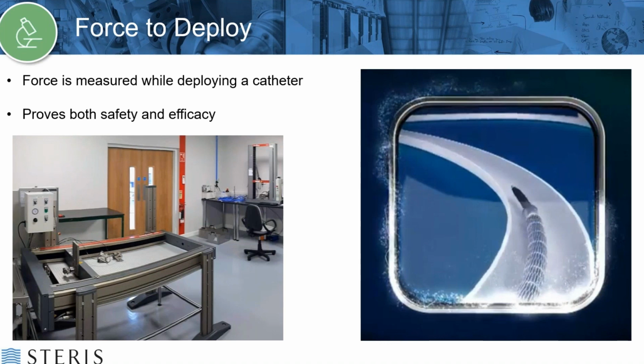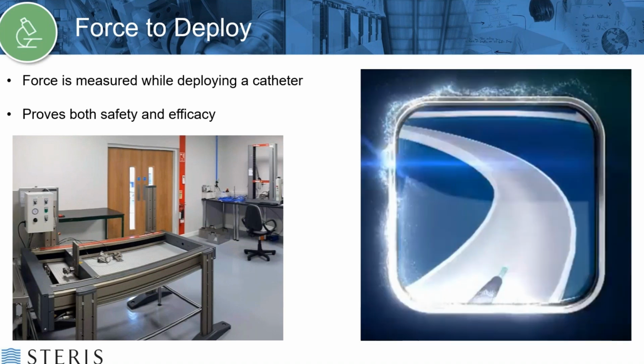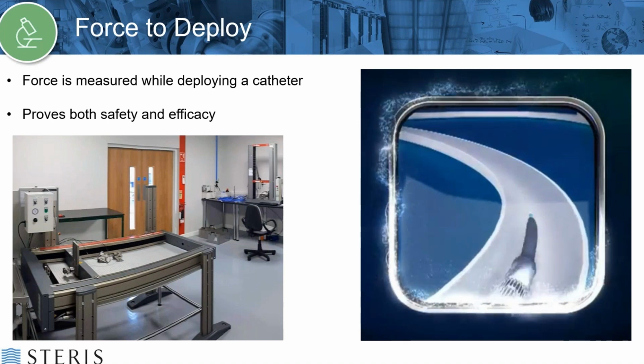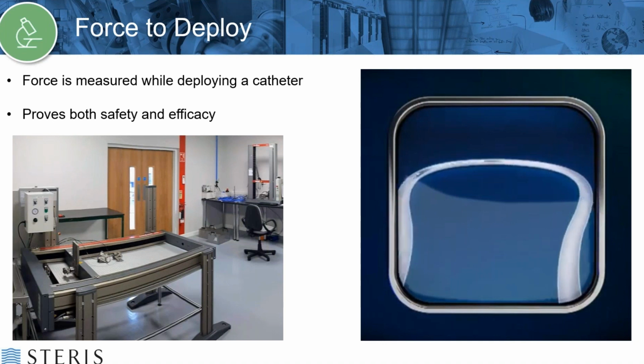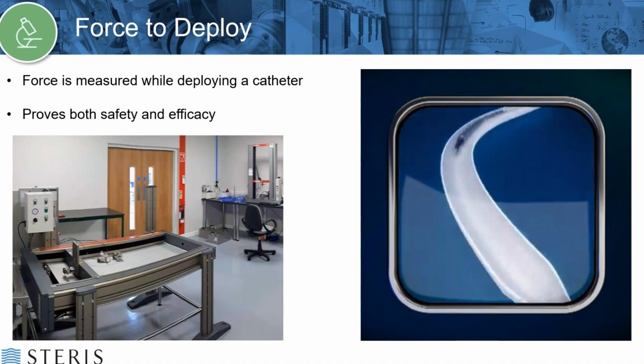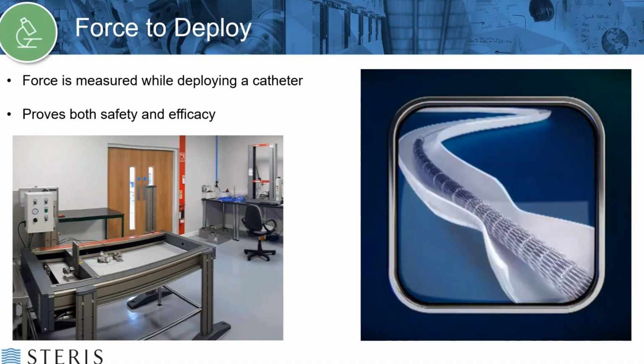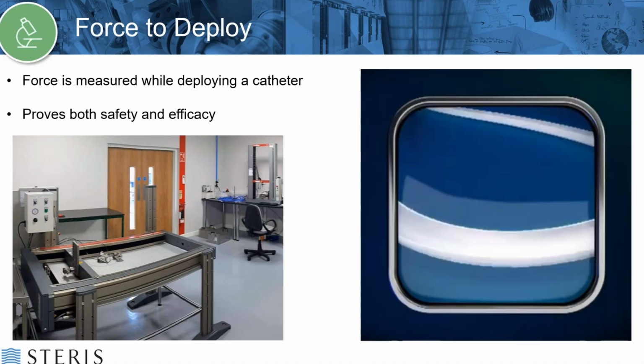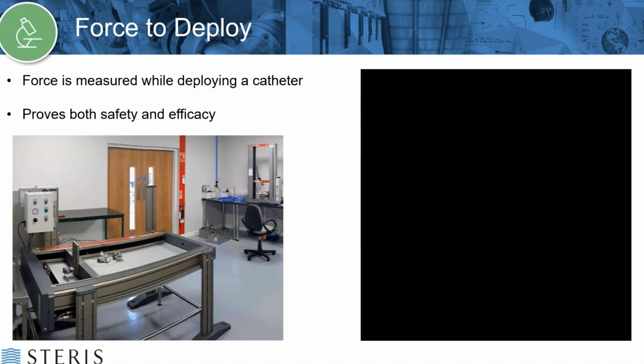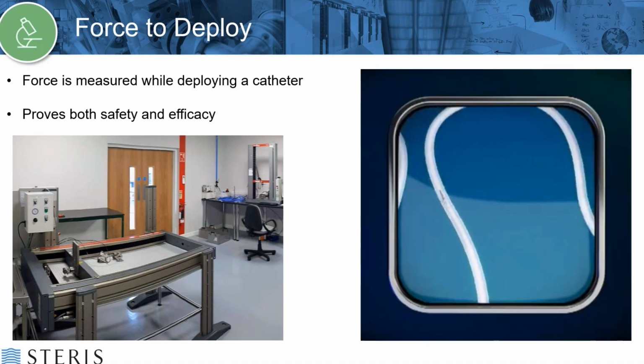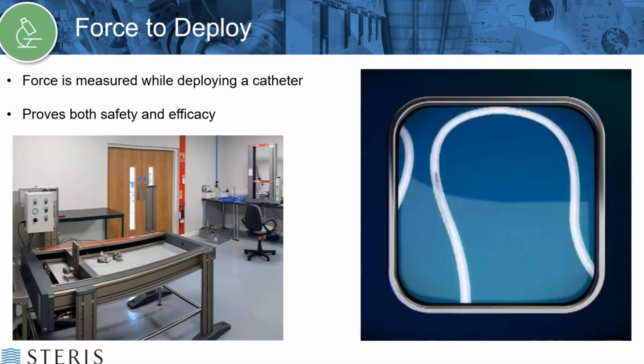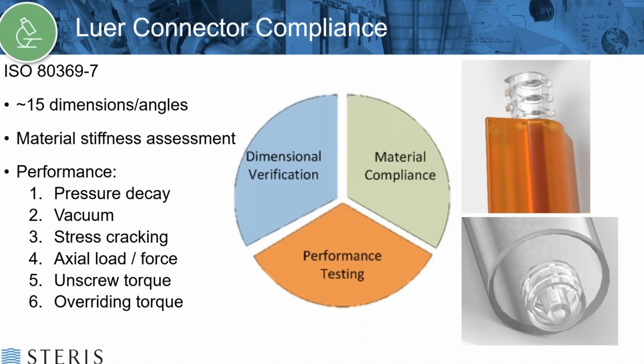Force to deploy is another test that is often used as a mechanism to assess the safety of a device. A delivery system with a stent tracking through a tortuous path. We simulate this on a horizontal tensile tester as seen in the image on the left, where a track model is located in a temperature-controlled water bath, positioned in the test bed, and the test system introduces the delivery system through the tortuous path and measures the reaction force down the delivery system, again proving both safety and efficacy of a device.